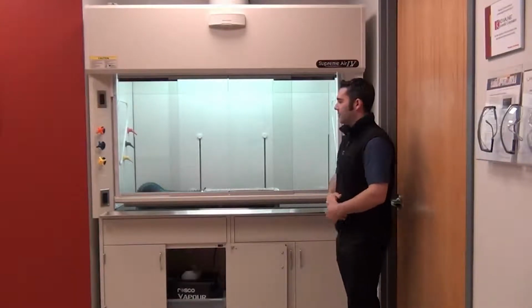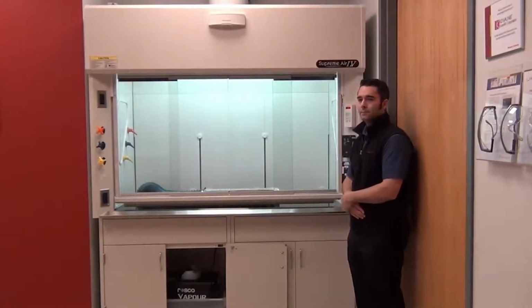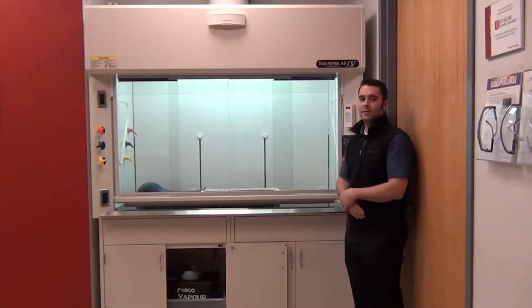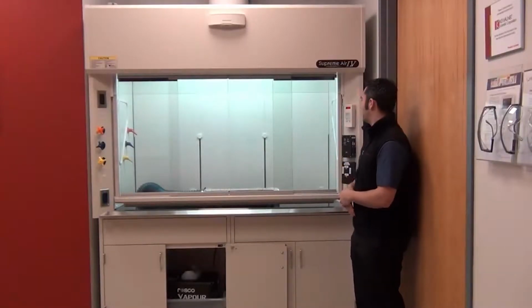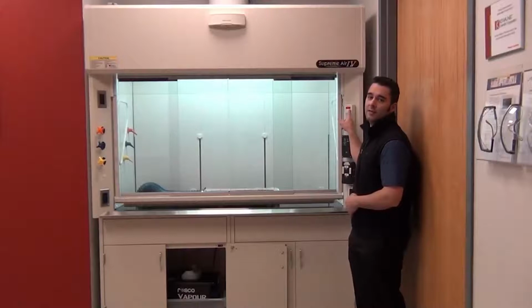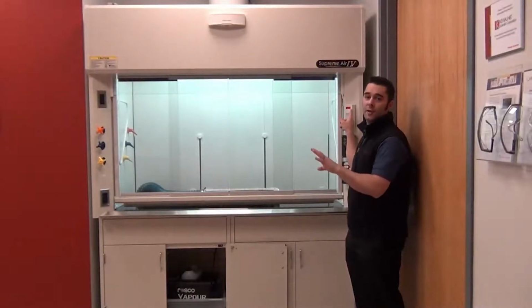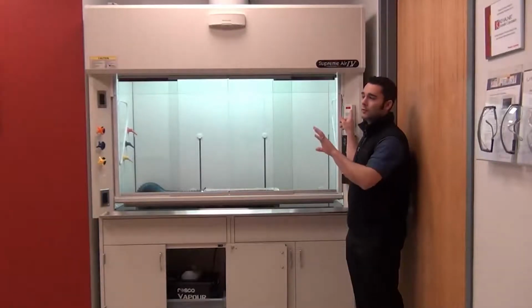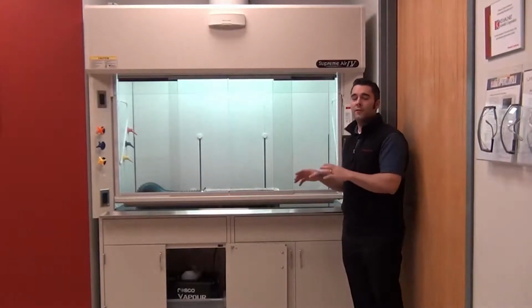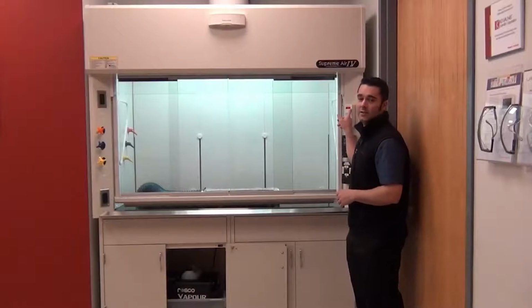So through a key sequence on the fume hood, I just shut this down to 0 CFM. And you probably can't see it on the camera, but this monitor actually indicates off. On the Sentry fume hood display, it will actually show fume hood in hibernation mode, so that there is no mistake that the fume hood is in hibernation mode, or in this case, off.